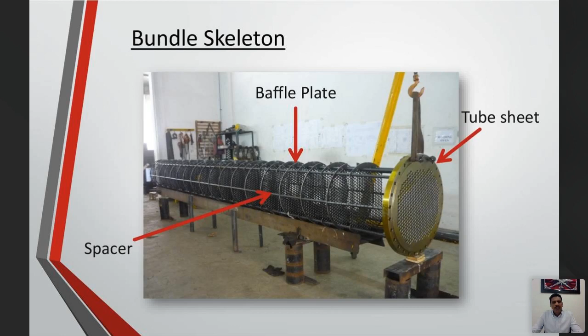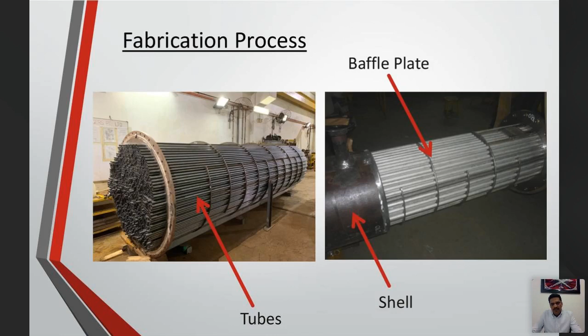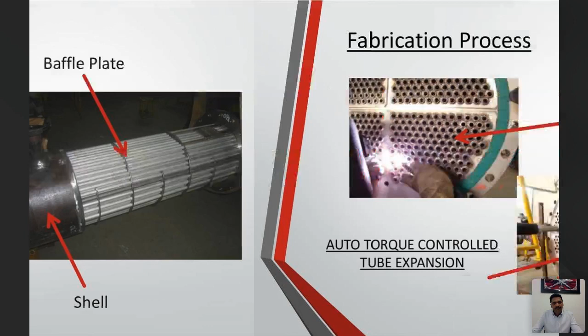This is the completed bundle with all the tubes inside. Then this is the area where the bundle is going inside the shell before welding the tube sheet onto the shell. After assembling the shell and tube sheet, the tube needs to be welded or roll expanded. Again, it depends on the pressure. Say for example, if you have 50 bar pressure, only a torque controlled tube expansion is not enough. So the tube end has to be welded. If it is low pressure, you need not do welding, you can just do a rolled expansion.